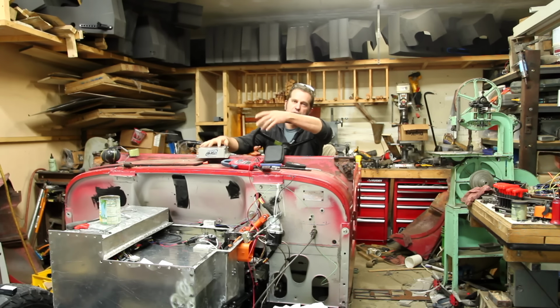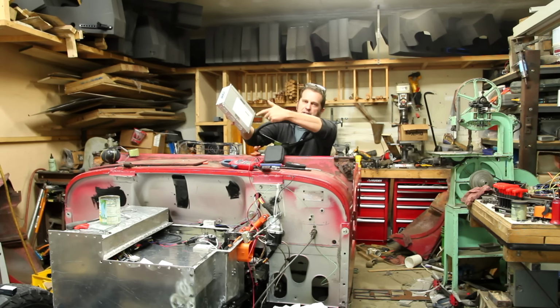So I looked up the troubleshooting procedure for that code for the Orion BMS, and it said to swap two connectors and see if the problem stays in the same place. Even with one of the other connectors in there, it was still on cell 65, which means it's an internal issue with the BMS, which means this gets to take a trip back to the factory in Illinois.